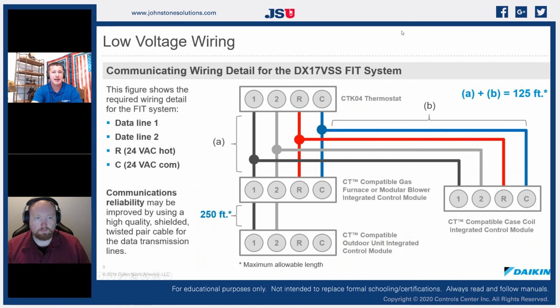Well, it comes down to understanding that whole DC communicating network. If we look at the wiring of a communicating system, and this is for the Daikin, but it's for everybody, at the thermostat on the Daikin, we're going to have 1 and 2, that's our communicating DC voltage, and we're going to have 24 volts AC that's feeding the thermostat. So that could be that CTK04, or it could be the new 1+ thermostat, which is a really cool thermostat. They're both talking the same way. That CTK04 was the first thermostat that Daikin used. It was built by Honeywell, and now the new Daikin 1+ is built by Daikin, but they are wired in pretty much the same way.